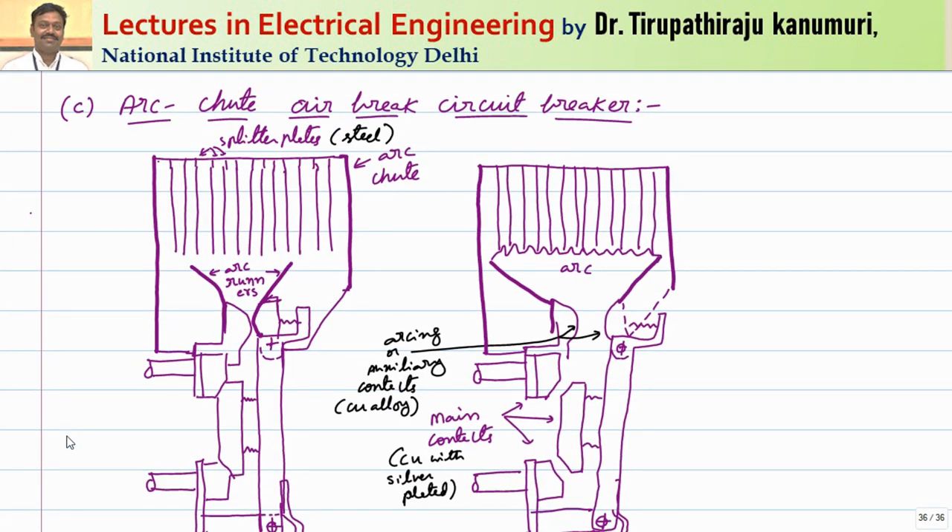There is one more technique used in practice: the arc chute air break circuit breaker. In arc chute air break circuit breakers, several splitter plates made of steel are inserted in the path. In the previous two methods, only single terminals are used for both normal and fault conditions. The problem is that under fault conditions, enormous heat is produced, and if normal copper is exposed to that temperature, the contacts may be damaged. To avoid this problem, the contacts are divided into two separate contacts. One is the arcing contact, also called the auxiliary contact.